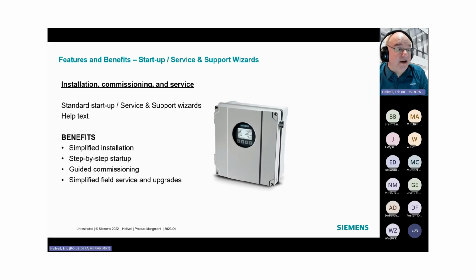All right, so built into the device, when you actually set it all up and turn it all on, is a startup and service wizard. The wizards within this device step you through the initial settings and the initial setup of the device. And if you stare too long at a screen, if you're waiting too much, it'll ask you if you need help, and it'll give you a hint as far as where to go and how to get it done. So setting it up on a meter, your first meter may take an hour, your second meter may take 40 minutes, and after that it's about a half an hour, unless it's a portable, in which case it happens even faster because you save the location that you're putting it on.